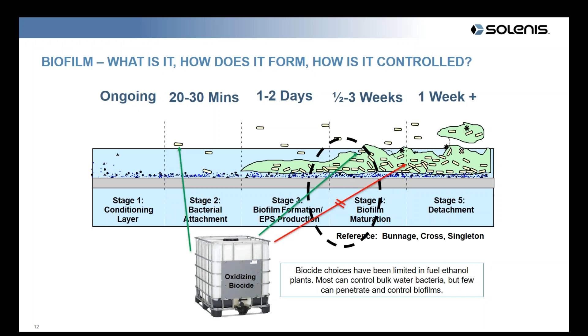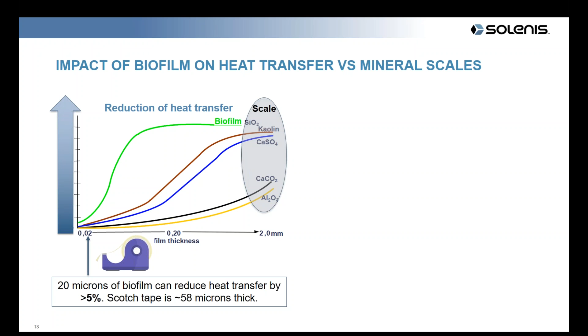Biofilm can have a huge impact on your heat transfer versus, say, a mineral scale, which you're all real familiar with. But what you really need to understand is that a thickness of biofilm is 4 to 5 times more insulating than the same thickness of scale. So 20 microns of biofilm can reduce your heat transfer by about 5%. If you think of that in terms of something we can all relate to, Scotch tape is roughly 58 microns thick, and the glue on Scotch tape is about 38 microns thick.